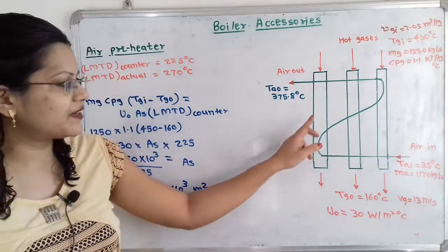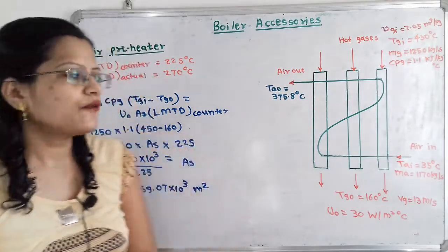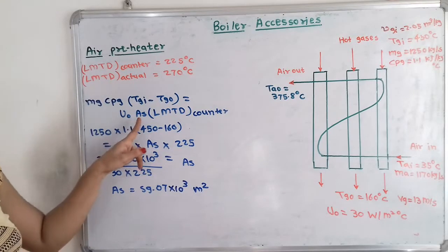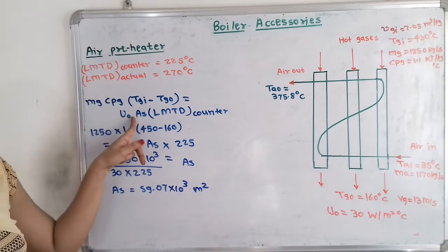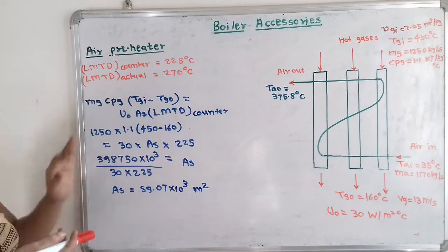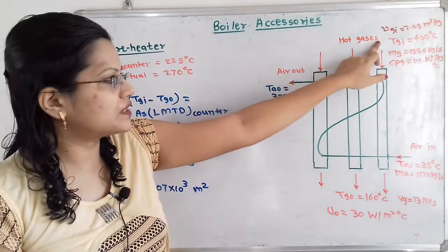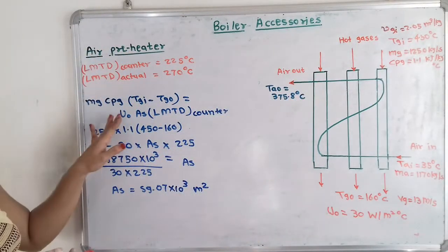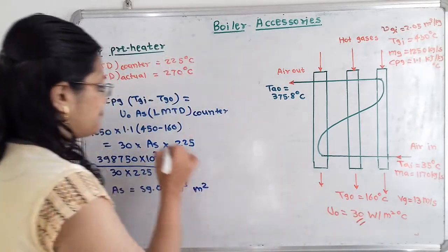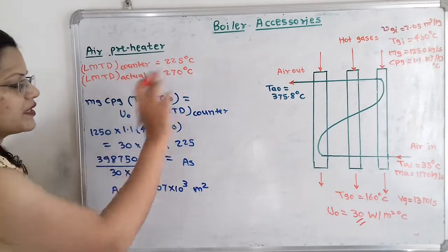Now we calculate the total surface area of the tubes using the heat transfer formula: Mg times CpG times (TGI minus TGO) equals UO times AS times LMTD counter. Substituting: 1250 times 1.1 times (450 minus 160) equals 30 times AS times 225. UO is in Watt per meter square degree Celsius and AS is the unknown surface area in meter square.